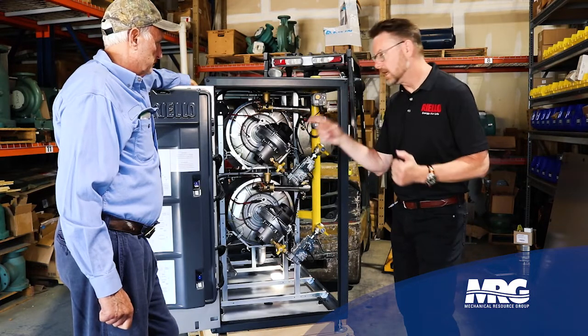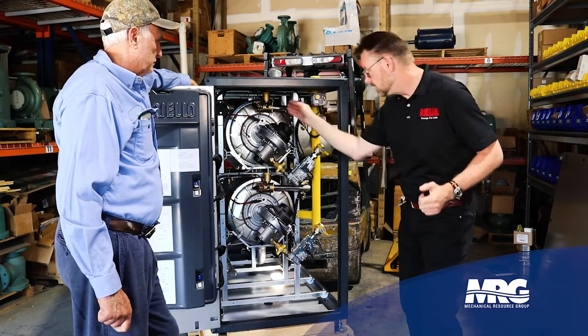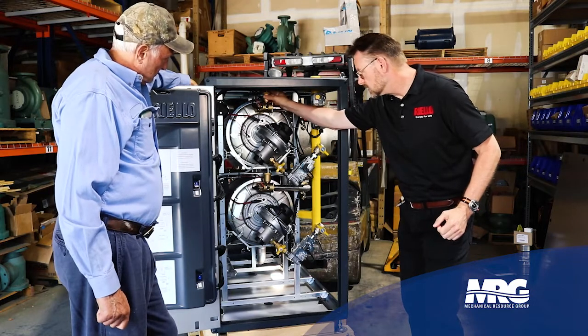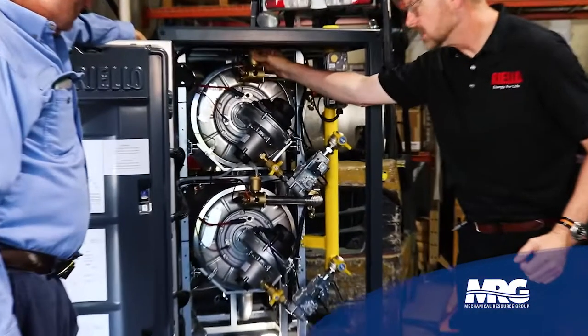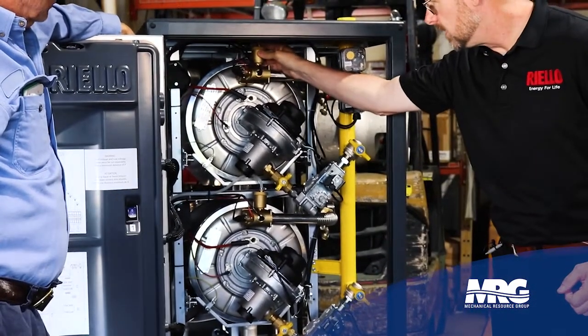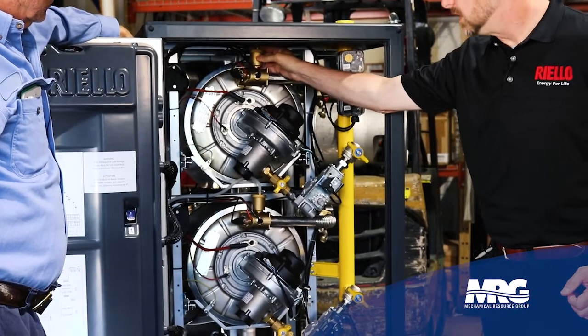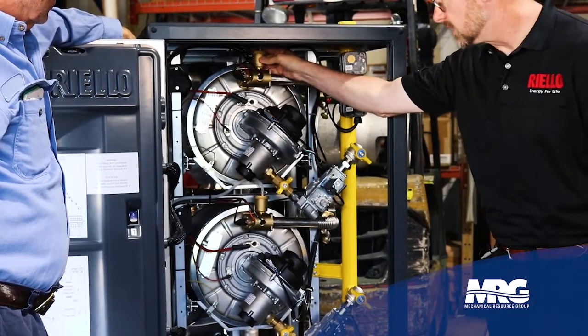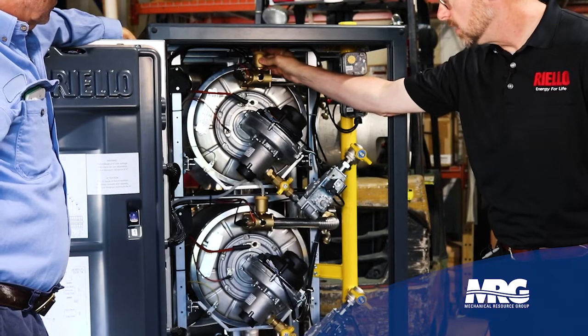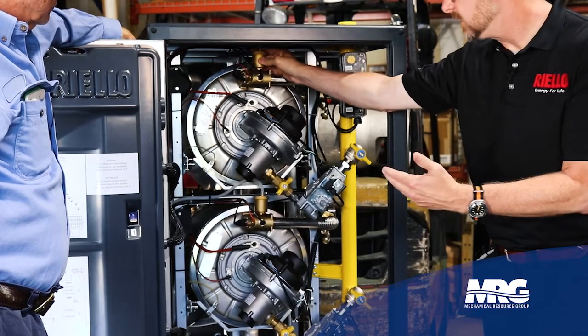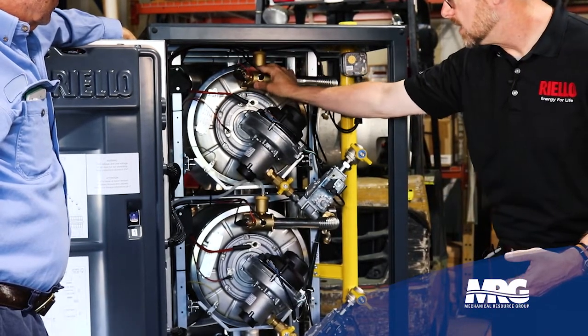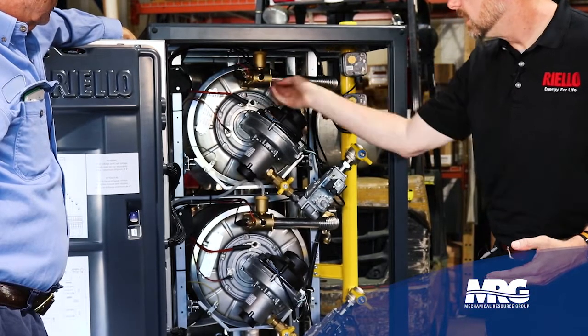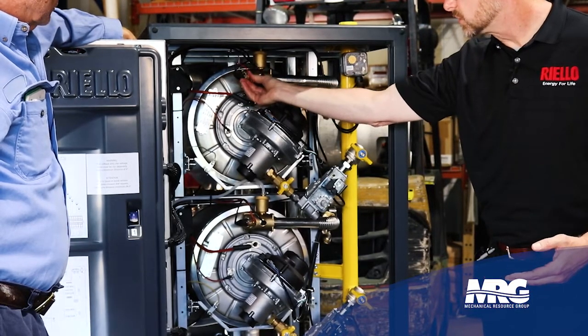We do have, unlike maybe that appliance was a little different, on each of the heat exchangers where the hottest water is going to be produced, we have a point of air elimination. And so it would follow that perhaps the failure of this air elimination or outrunning its ability to eliminate the air might cause there to be air present here rather than water, which would in fact accurately trip the low water.